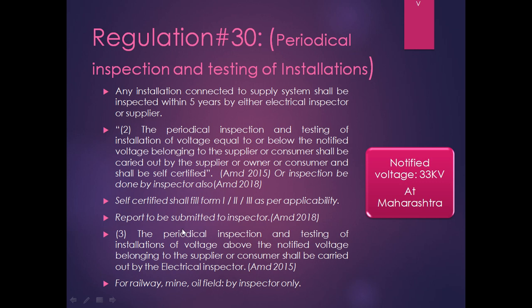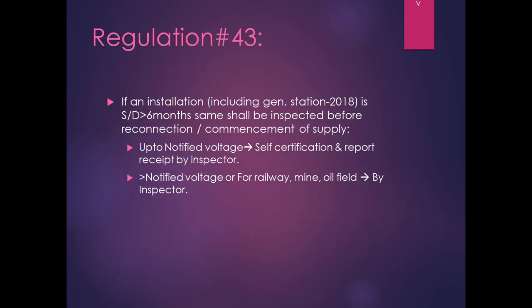Next point, the installation whose voltage level is more than the notified voltage, they have to call the inspector for inspection. Next point, the railway, mine and oil field shall be inspected by the inspector only, irrespective of the voltage level. In this regard, there is another regulation, regulation number 43. It says if an installation including a generating station is shut down for a period of more than 6 months, the same shall be inspected before reconnection or commencement of supply.